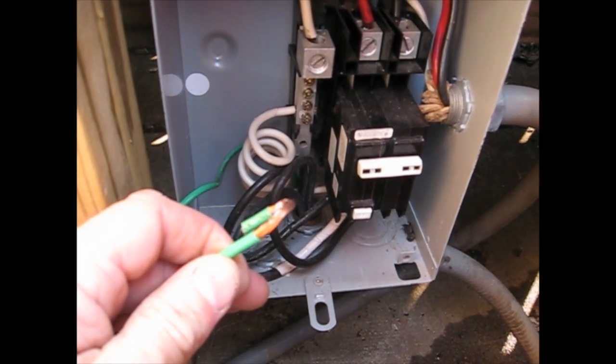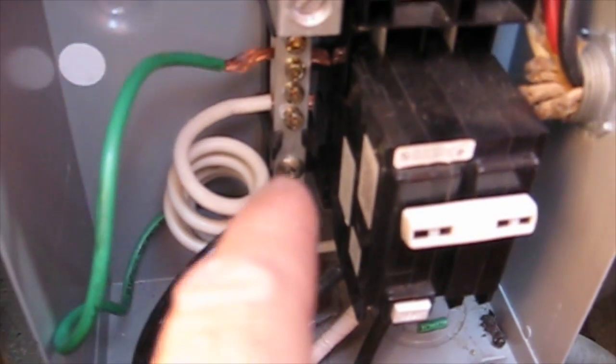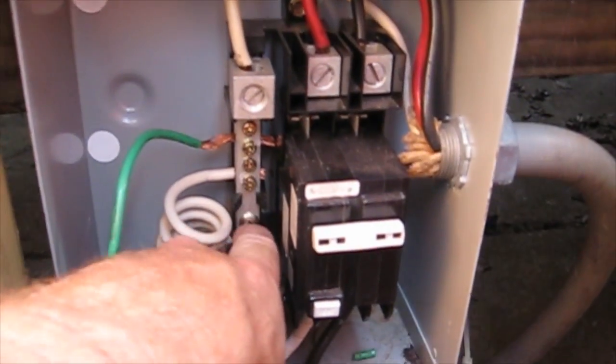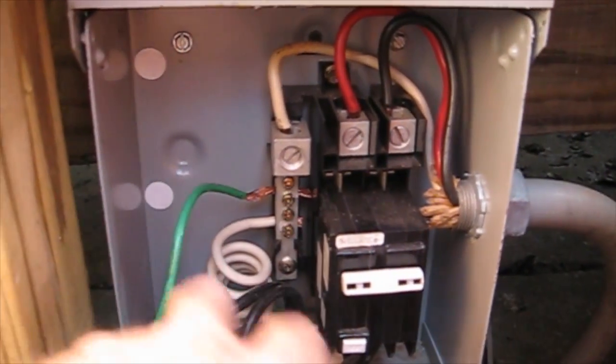And on the same system, somebody had removed this screw. So this block was not grounded to the box. The metal box has got to be grounded. And so I installed a screw back in here. So this thing is complete and running like a champ.